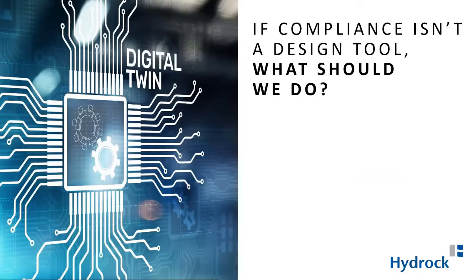So if compliance isn't a design tool, I should say, compliance works absolutely fine for what it does, but it isn't a design tool. You shouldn't be designing to compliance, and I will give an example later on about why there can be some issues with that. There has been some effort to separate out these compliance models from the predicted energy performance models, and those are generally CIBSE TM54 and CIBSE TM63. Those are predicting energy use at design stage, that's TM54, and making your building work at post-occupancy, which is TM63. An example I'll go through is the intention of TM63. It doesn't follow the criteria exactly, but it's close to.